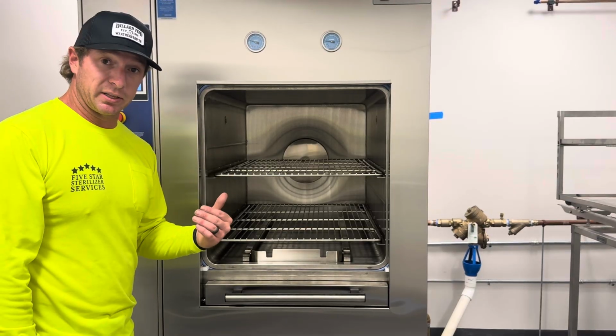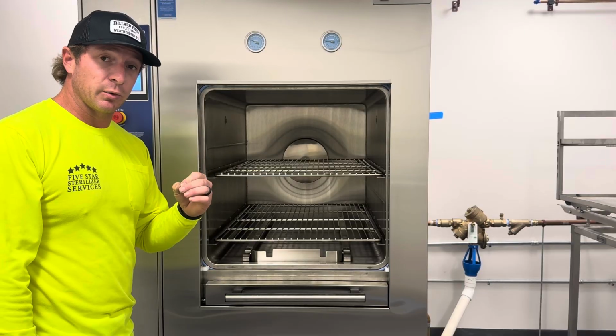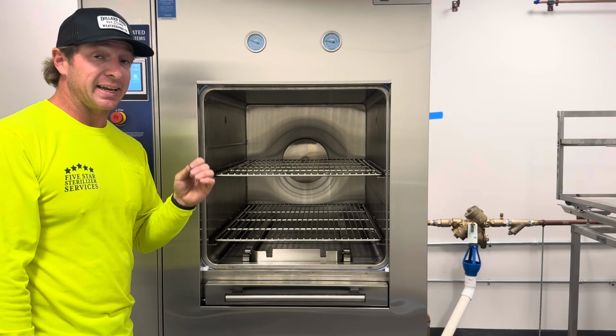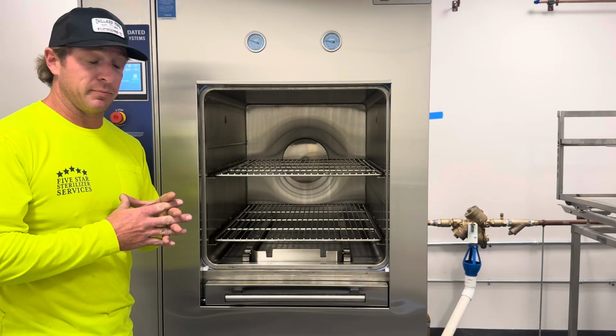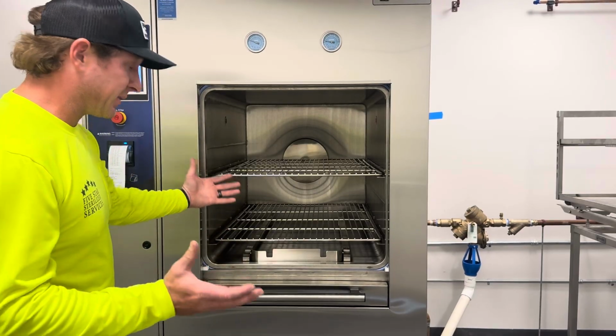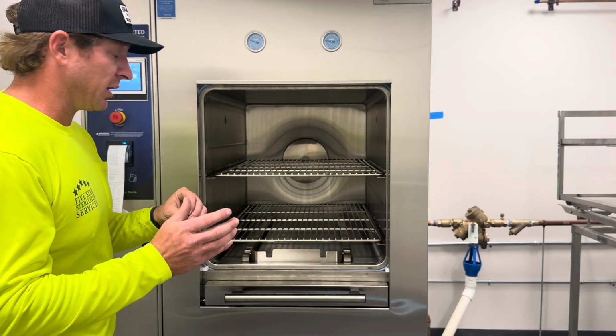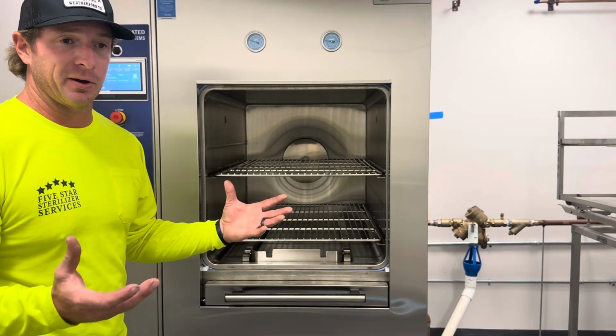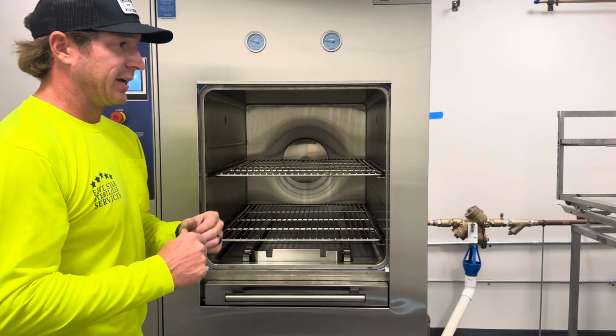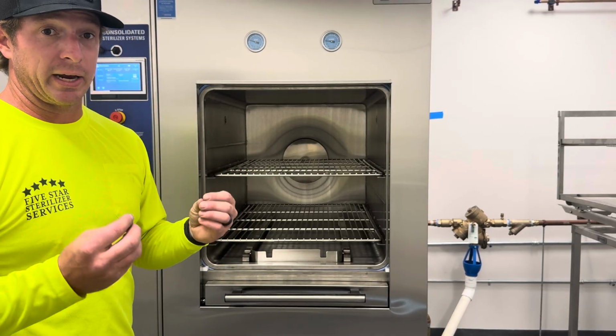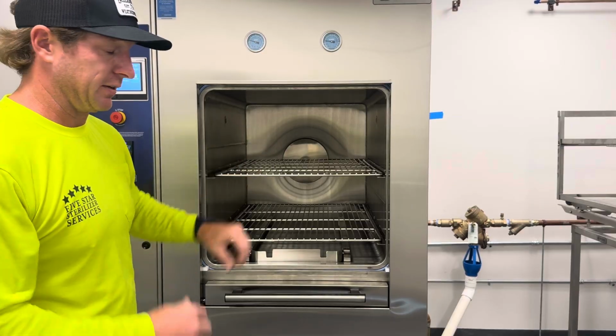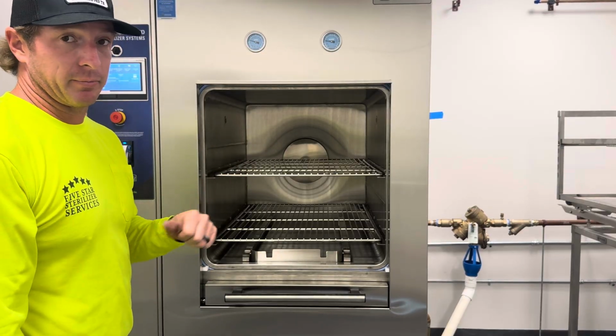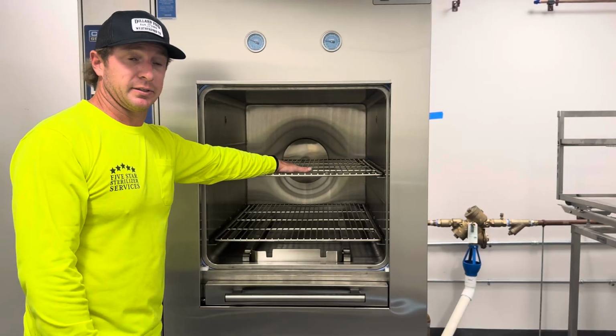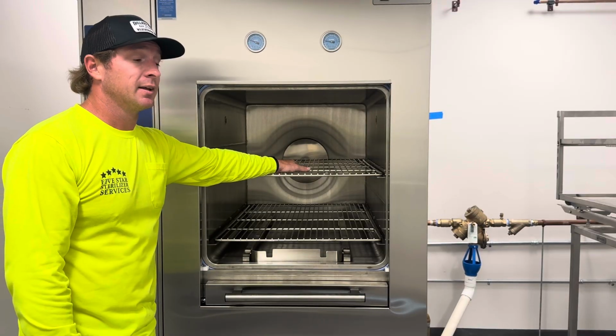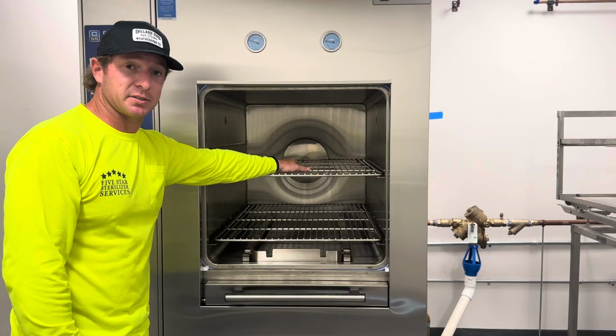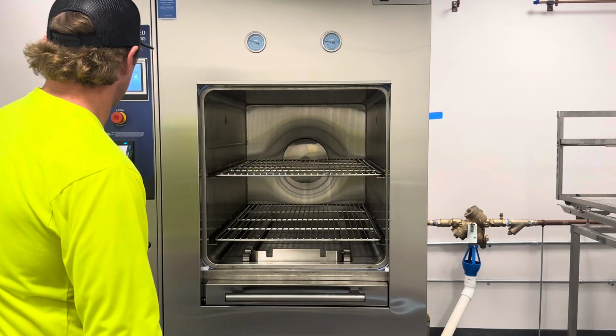and if you're running a liquid load, you must put all liquids inside a tub, not just any tub, an autoclave approved tub, either a stainless steel tub that can contain any spills or boilovers, or like Thermo or Fisher Scientific, they sell autoclave temperature rated tubs specifically for autoclaves. Do not go to Walmart or Target and buy just a tub off the shelf and try to run it in here. It's going to melt it, it's going to wind up in the drain, and it's going to cost the university a lot of money to fix it.